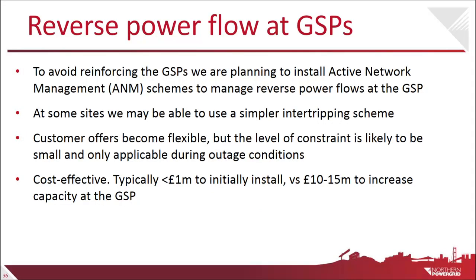So reverse power flow at GSPs. We have a number of transformers at the grid supply point that have a thermal rating, and as we go into reverse power flow, we've got to make sure that we don't overload those assets. Those assets are classed as transmission assets. We already make those assessments on our distribution networks, but we need to make sure we don't overload National Grid's assets either. Now, under normal running, this generally isn't an issue, but when we have planned outages in the summer, we can get into some situations where the theoretical reverse power could be too high, and we would need to constrain some customers. But generally, it's only if we have a planned outage followed by a fault, and we're left with maybe one transformer out of 3 or 2 out of 4, and they struggle to cope with the reverse power at certain times of day.